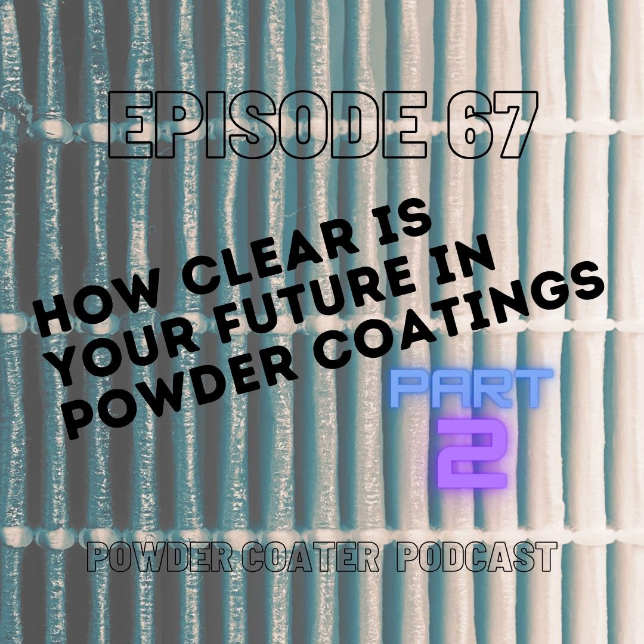So we often look at our boost inquiries as people who can't keep up. Mm-hmm. Their oven, they just can't get the throughput. They can't get their part cured. They're not getting enough temperature, either because they're going faster or because they have a harder part, or the powder they've selected. The powder selection can have an impact on this, because just because powders have the same temperature, they don't all cure the same way, depending on how much filler they have.